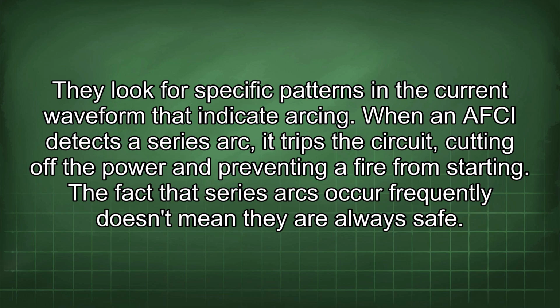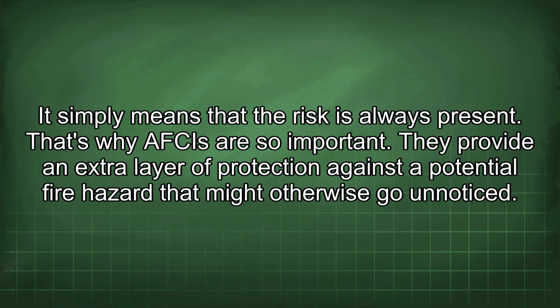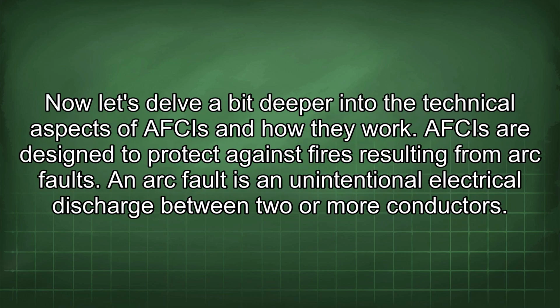When an AFCI detects a series arc, it trips the circuit, cutting off the power and preventing a fire from starting. The fact that series arcs occur frequently doesn't mean they're always safe. It simply means that the risk is always present. That's why AFCIs are so important. They provide an extra layer of protection against a potential fire hazard that might otherwise go unnoticed. Now let's delve a bit deeper into the technical aspects of AFCIs and how they work.